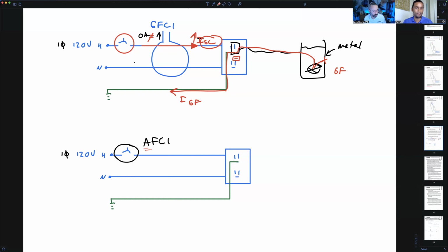You're going to have a little bit of arcing on normal everyday use at 120 volts. It's to be expected, right? When we plug something in, we're literally taking a metal thing and shoving it into the metal prongs of the receptacle, right? When you get 480 volt motors, there are arc chutes built into the breakers and lugs and all that. At 120, it's not really as dangerous. It's no big deal to just shove a metal thing into another metal thing. But there's always going to be a little bit of arcing.